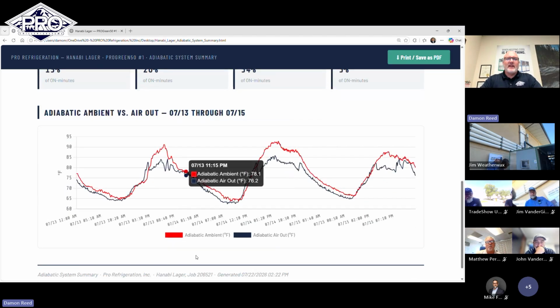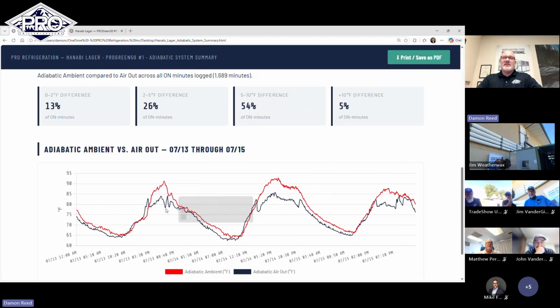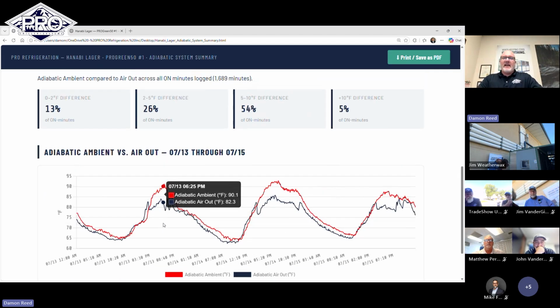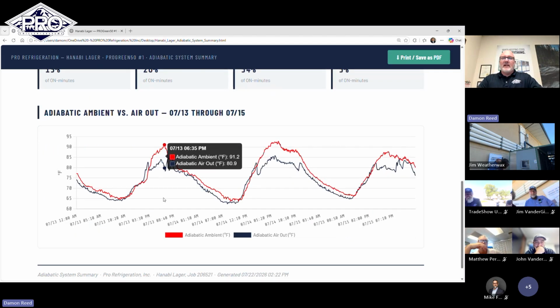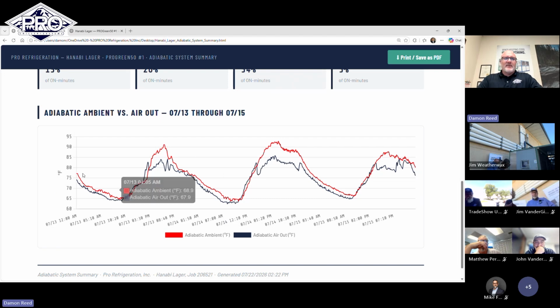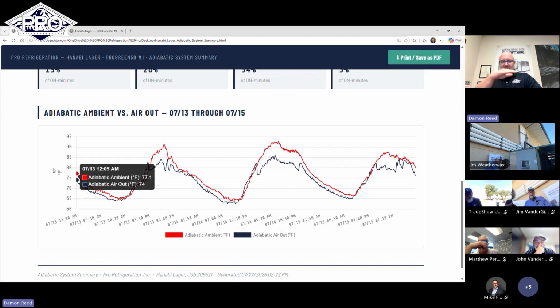Broken down here, there were a few days, the 13th through the 15th, where we had a hot spell, if you will. Those are our biggest run periods for adiabatic. So the ambient temperature is the red line, and the air coming out of it is the blue line. The average of the high of the adiabatic air out was 81 degrees.